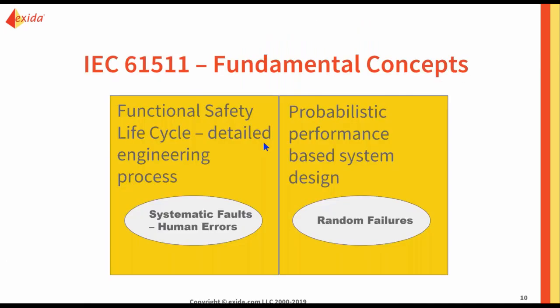In IEC 61511, and in all functional safety standards, there are two fundamental concepts. First, protect against what are called systematic faults — mostly human errors like software bugs, bad calibration instructions, and things of that nature. Second, protect against random failures. A detailed engineering process is the defense mechanism against systematic faults, and a probabilistic performance-based system design is the defense against random failures.